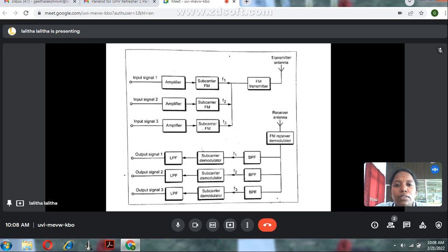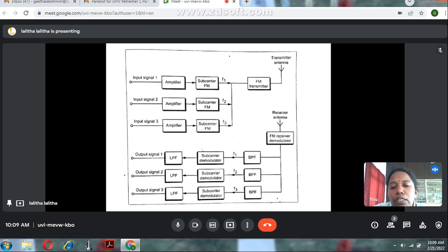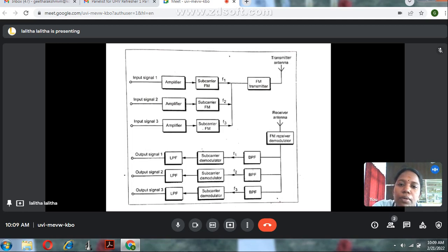The multi-channel telemetry system consists of frequency division multiplexing (FDM) and time division multiplexing (TDM). In FDM, the transmitting side consists of three input signals connected to amplifiers. The subcarrier system is used to eliminate the loading effect. Each amplified input signal is connected to a subcarrier FM, which eliminates the loading effect and produces frequency signals based on the three input signals.